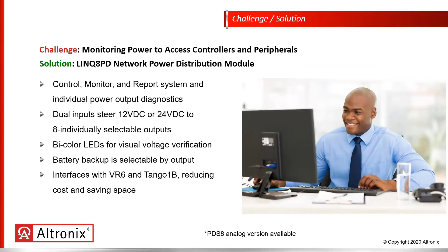The Link 8 PD now gives us the ability to drill down a little bit further. And we want to be able to monitor power to our access controllers and our peripheral devices that are connected up. And what the Link 8 PD gives us is the ability to take up to 2 inputs, so both 12 and 24 volts DC in, and then select per output 12 or 24 volts DC. Great for any application, again, where we require dual voltage and we have 2 power supplies.